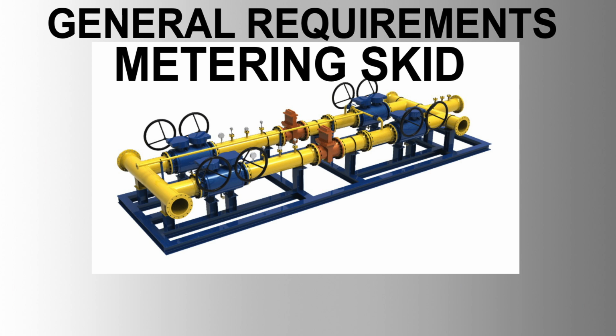Upstream straight lengths for ultrasonic meters should follow specific diameter-dependent lengths. USM DN 600 equals 40D, USM DN 500 equals 30D, USM DN 300 equals 23D. Flow conditioners can be used to reduce size and improve metering accuracy, provided the design is based on accepted practices and/or tests.